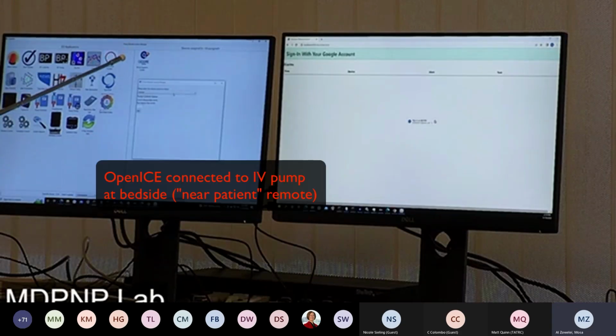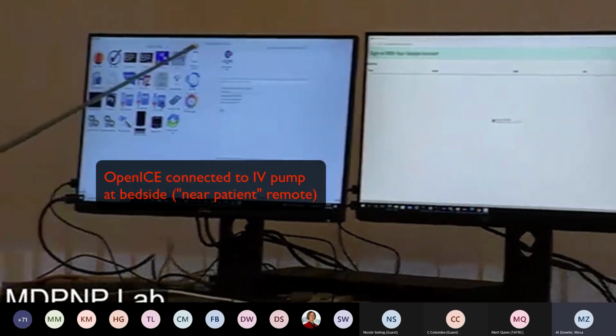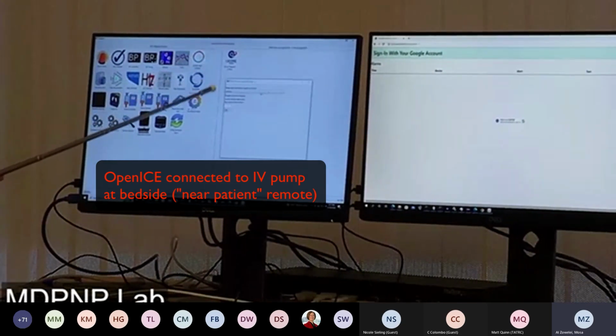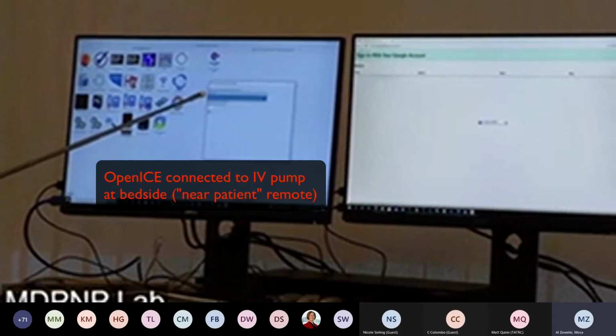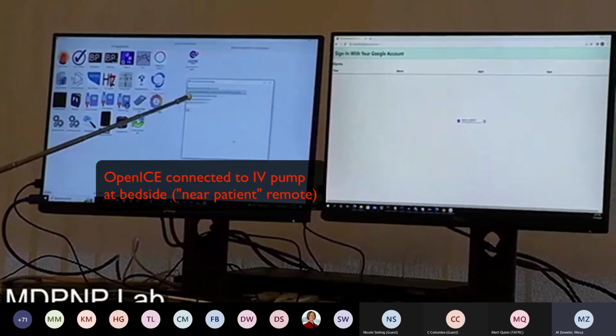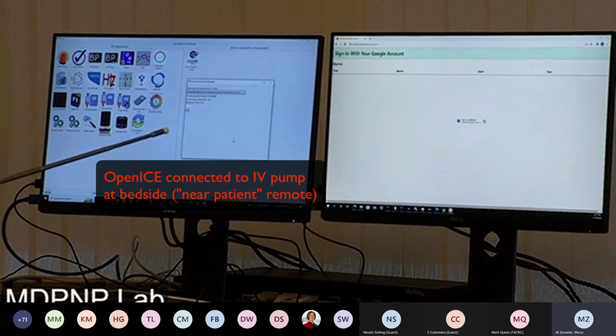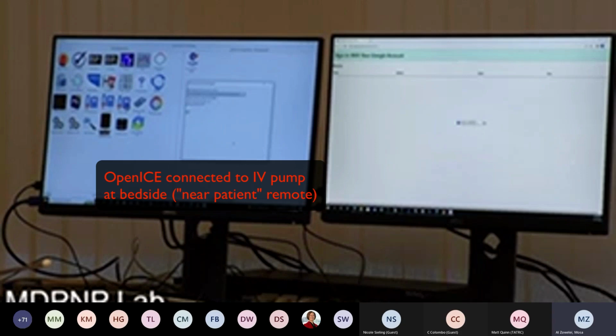So on the bedside computer, we're running our OpenICE platform. We have one infusion pump connected, which is this Sapphire infusion pump, and we're running a pump remote control manager application. In this application, we can choose our infusion pump, and we can see that the pump control status message is currently set to "by pump." What that means is that the rate that the pump is running at, which is 25 milliliters per hour, was programmed in using the touch panel of the pump, using the pump's user interface rather than through the application or the remote control.